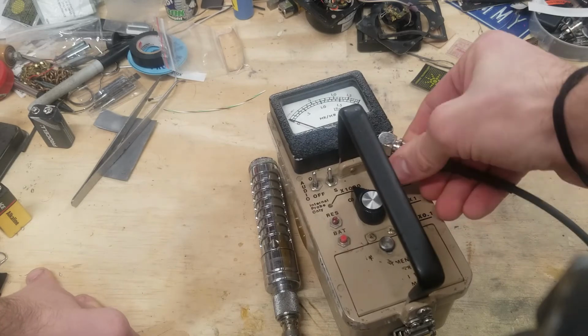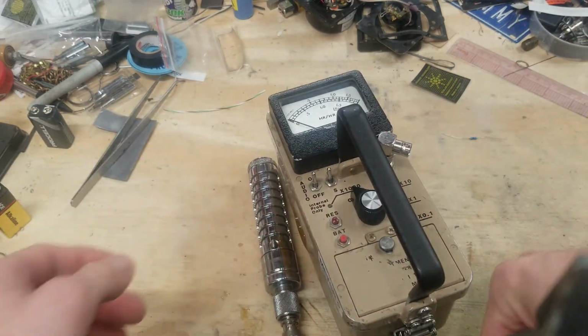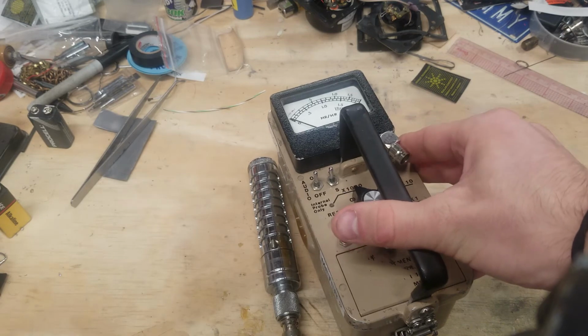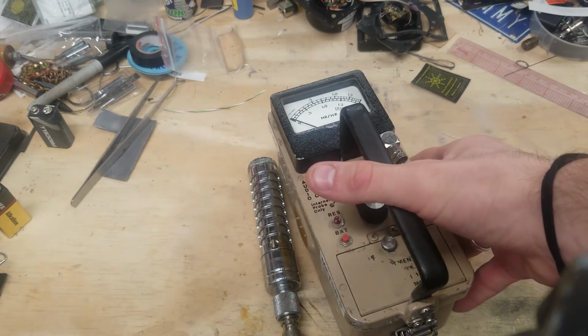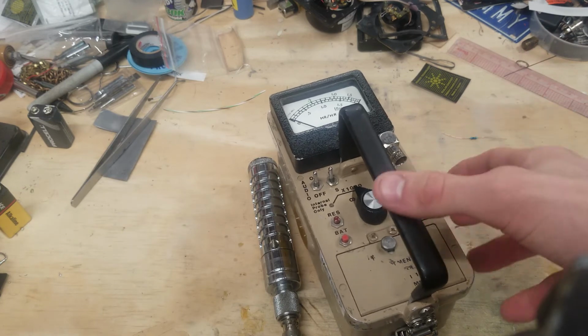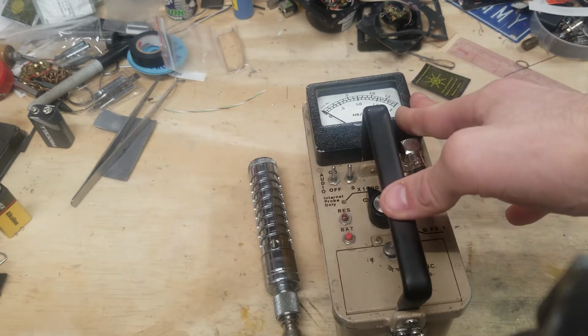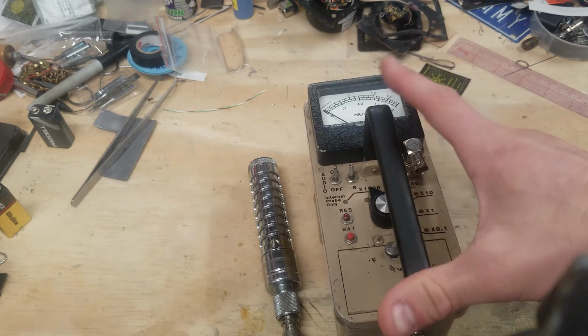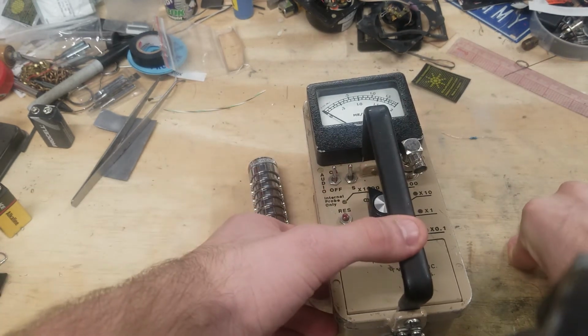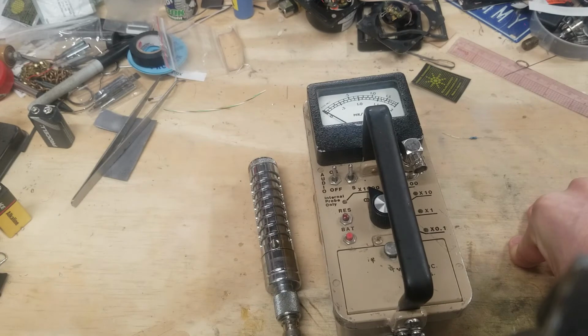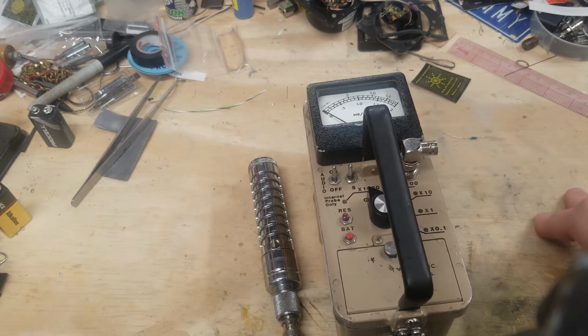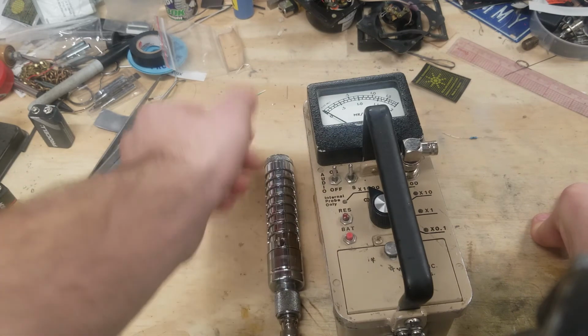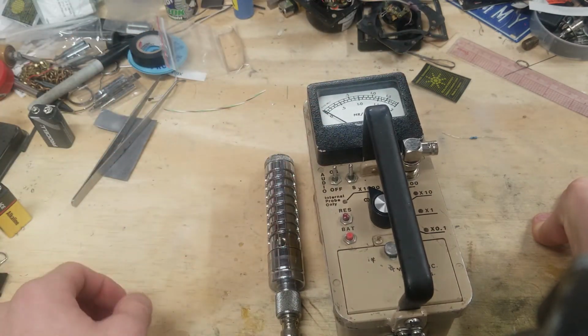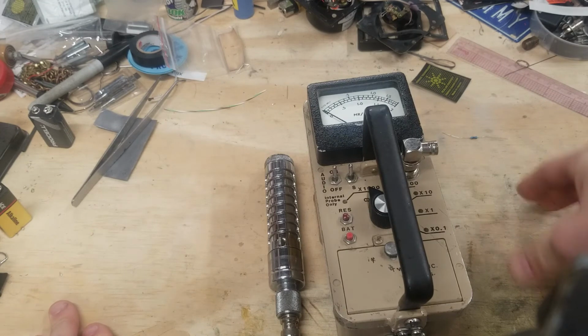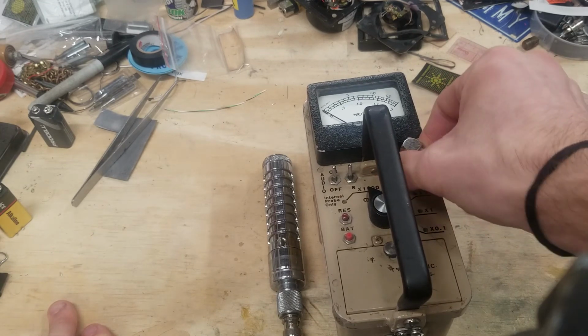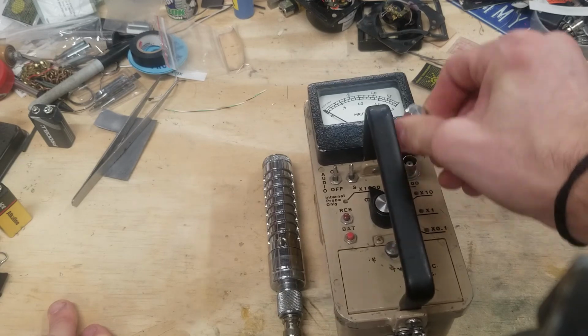They're nice meters, and in this case, this one is kept in its current configuration because it is ready to be sent for calibration, so I can use it as a dose meter. I don't trust the dosage as it sits right now. I'm not sure what its original probe was, or what its original calibration was for. I assume it was likely a pickle style probe, simply by just being a mR scale, but this I'm uncertain about. So until I have it calibrated, I can't say for certain that my dosage is 100%.